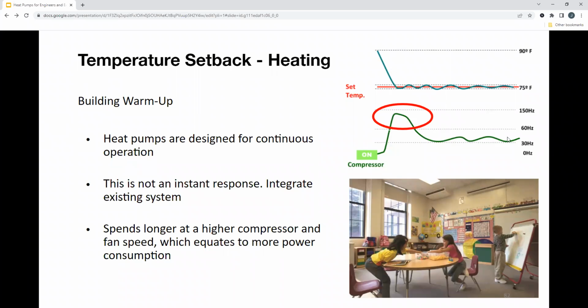So as I mentioned before, heat pumps are designed for continuous operation, right? So we want to keep this on. We don't want to turn it off ever. We want to keep this set point where it is, 75 degrees, and we want to ramp down the compressor as much as possible to use as little energy as possible. That's how it operates. With a building warm-up, typically you do a larger setback, right?